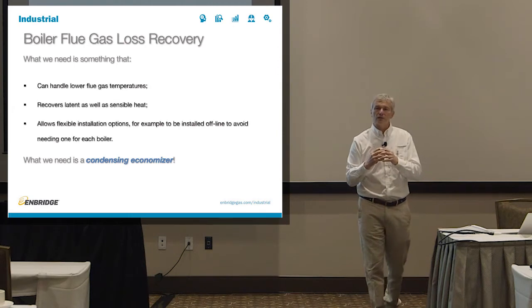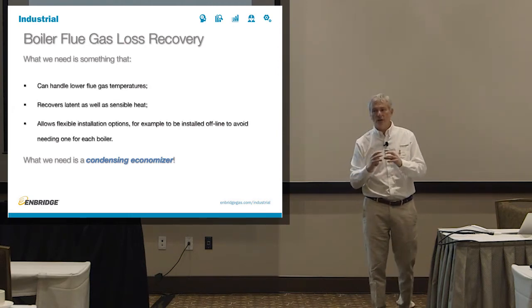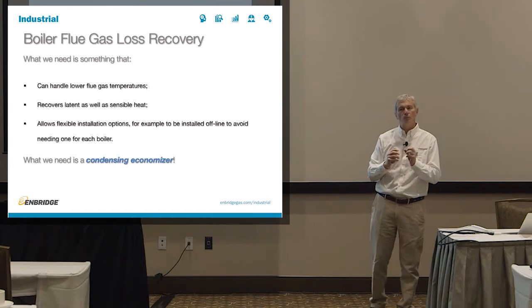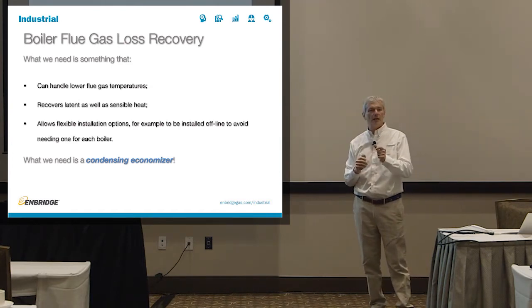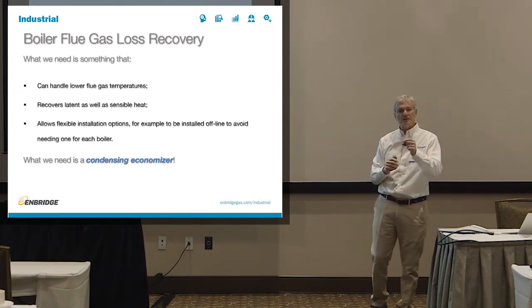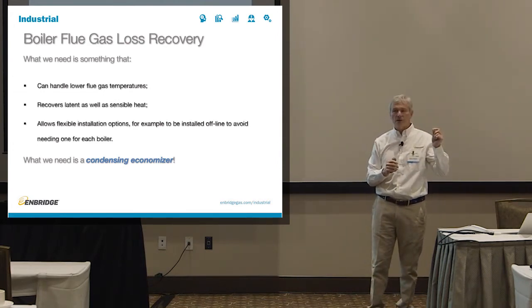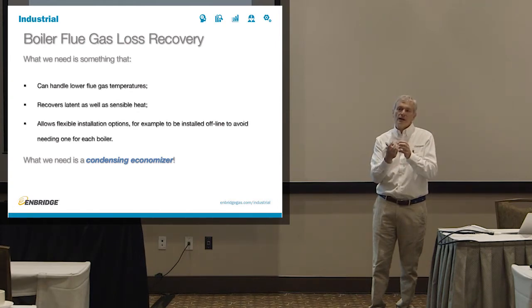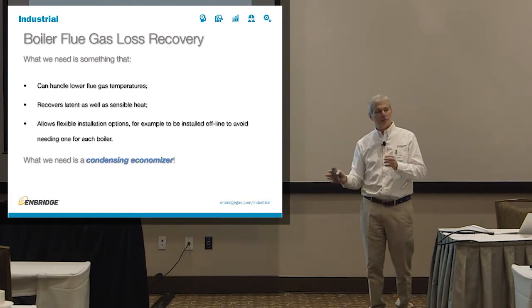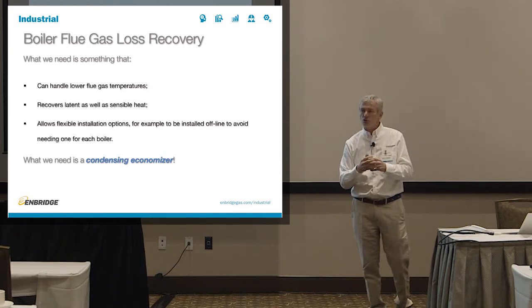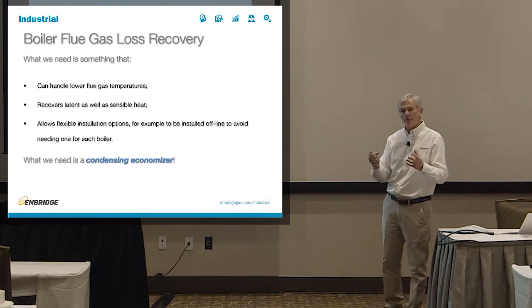And what happens in the flue gases of all sorts, not just in the boilers, any flue gas will have a certain amount of moisture in it, typically between 8 and 12%. So now that moisture is leaving together with the flue gas stream. If you can squeeze that moisture out, now you're getting that latent heat, that phase change energy back into your stream. So by condensing the moisture out of the flue gas, you will release about 1,000 BTUs for every pound of moisture back into your system. So you can get much more heat energy out of the same principle, essentially.